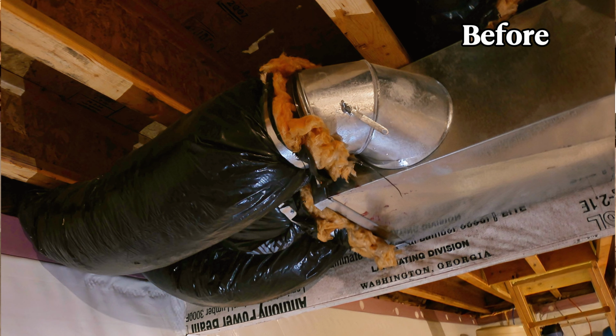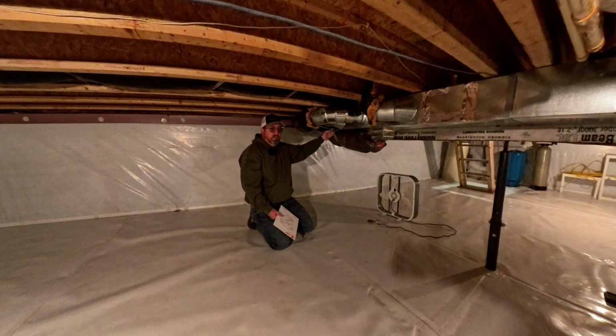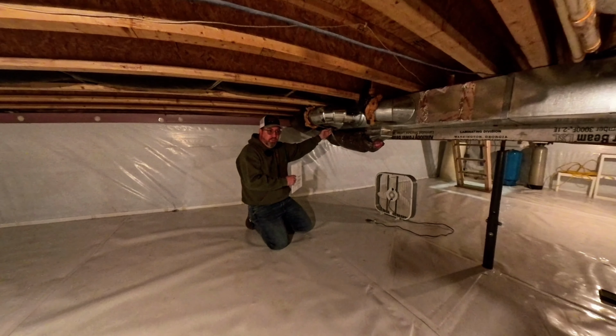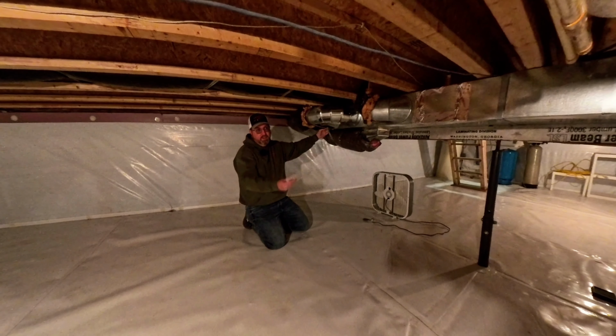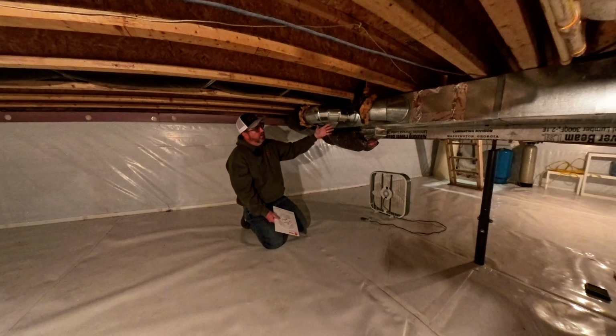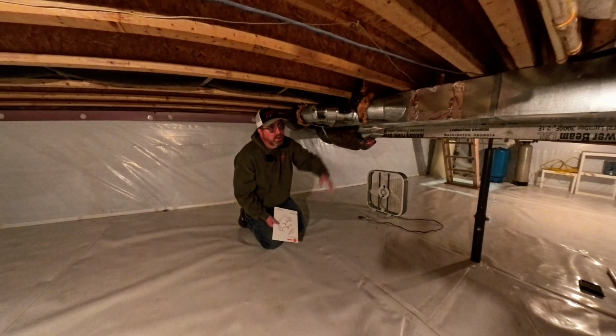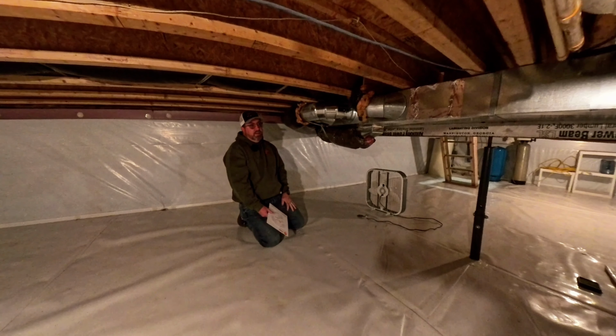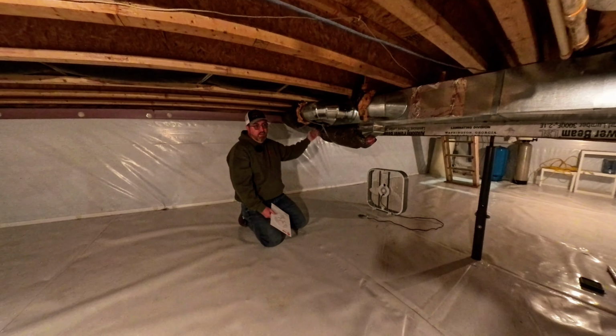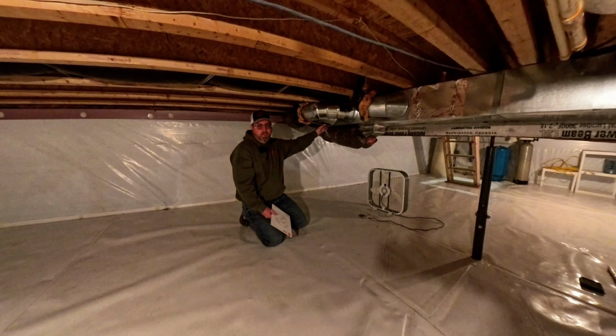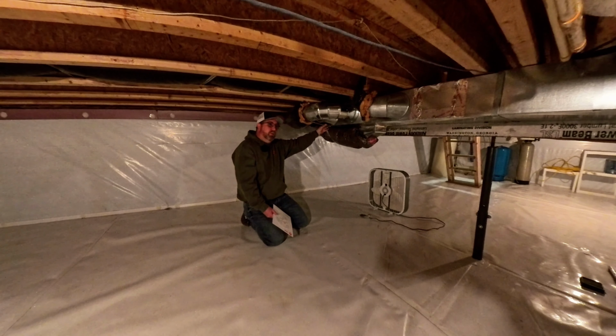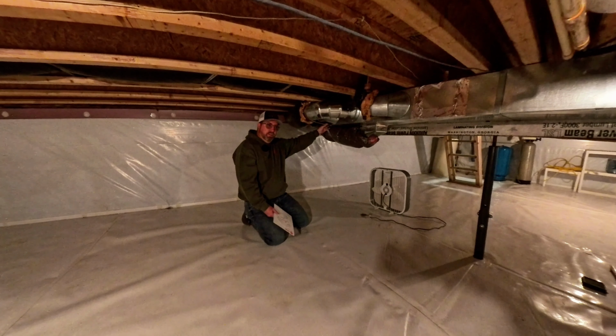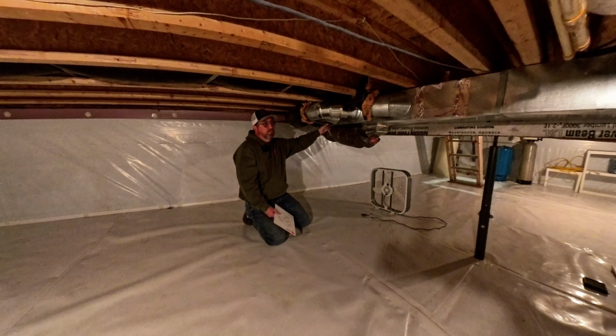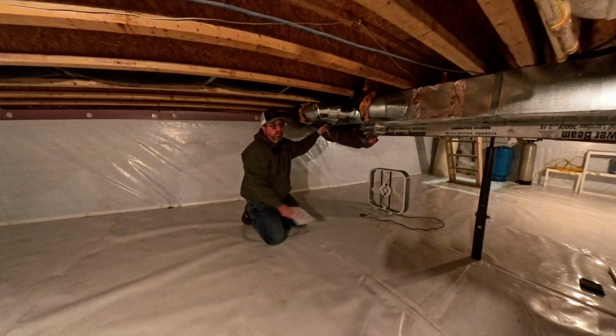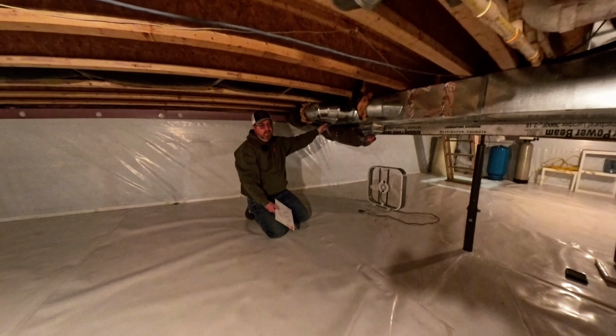And in the HVAC world, that is a big no-no with the ducting, because airflow runs down this duct system, hits this end cap, and it uses the end cap to pressurize the duct system so that airflow comes out all of these supply runs as they come off the duct system. If you have a bunch of holes in the end cap, that pressurization can't work. You get a lot of airflow out of the particular runs that come out of the end cap, but you lose airflow out of the runs that are not in the end cap.